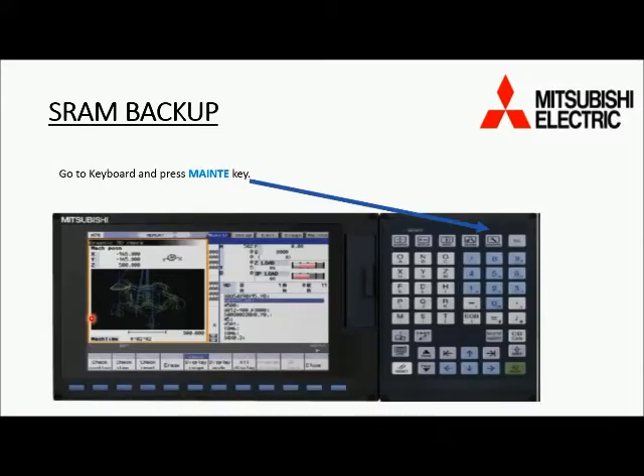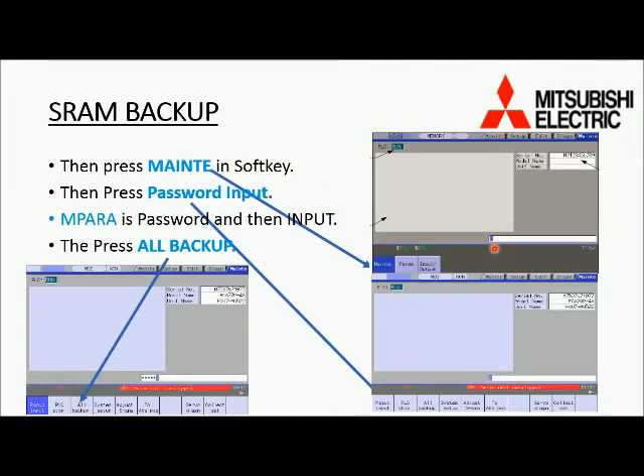Now we will see how to take SRAM backup. For this we have to go to the keyboard and press the MAINTE key. This brings up the first option in the softkey. Then a new page opens where we find the first softkey as password input. Press it and enter the password MPARA from the keyboard, then press input.